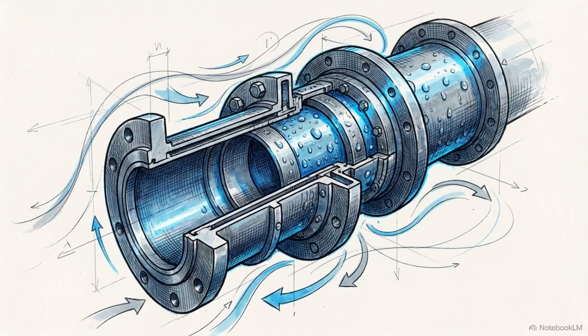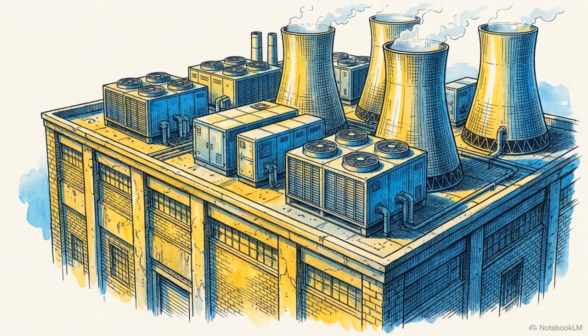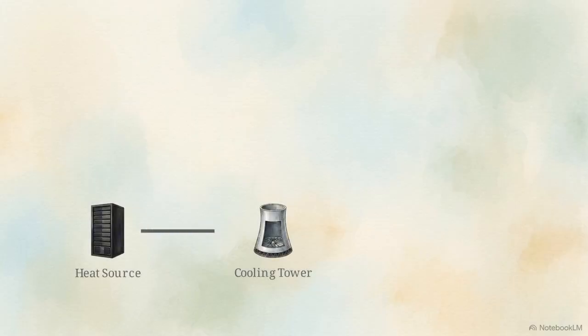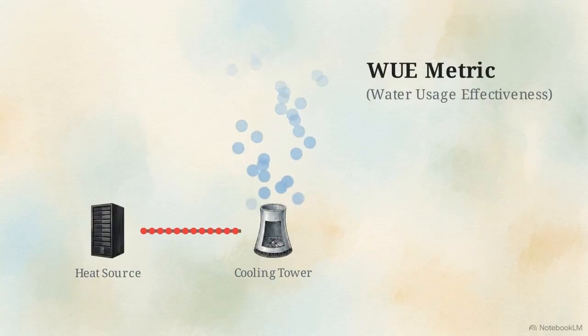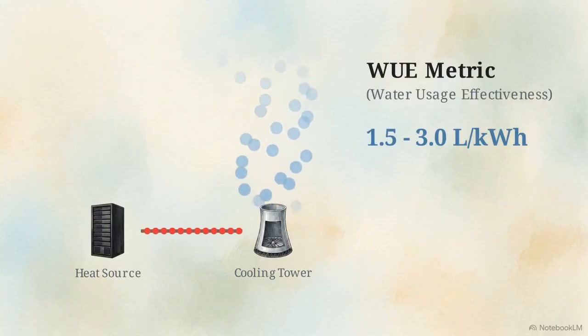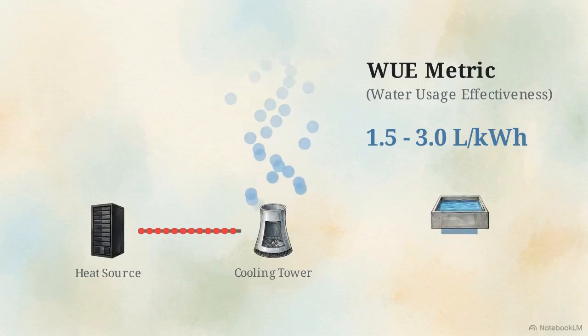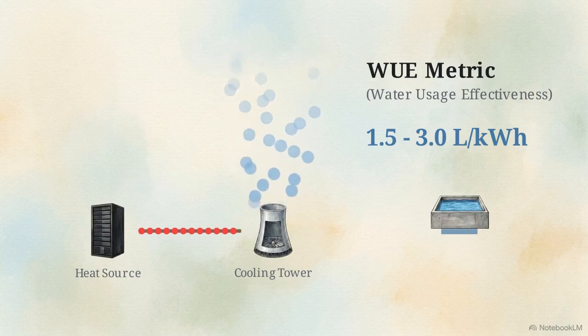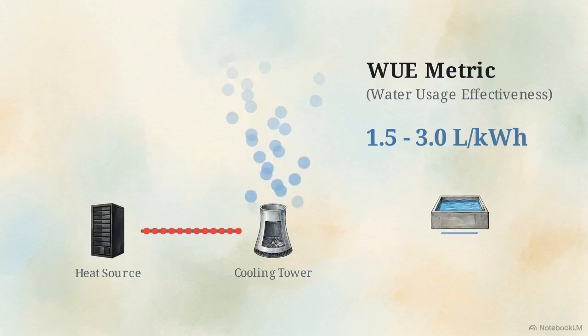Water is the traditional, highly effective medium for extracting heat from heavy industrial systems. For years, data centers have relied on legacy open-loop evaporative cooling. Looking at this schematic of an open-loop system, heated water is transported away from the servers and pumped into a cooling tower. There, it is exposed to the outside atmosphere, and the heat escapes through evaporation. To evaluate this fluid loss per unit of power, the industry uses water usage effectiveness, or WUE. Traditional evaporative systems post a WUE between 1.5 and 3.0 liters of water consumed for every kilowatt-hour of electricity.